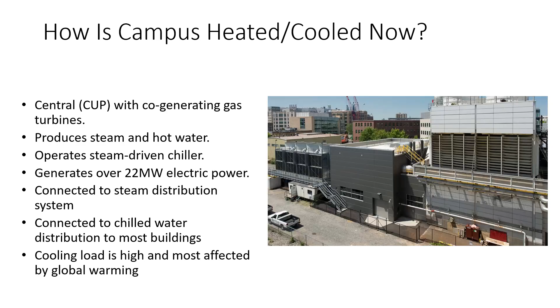Decarbonization issues with the existing plant: grid decarbonization is rapidly reducing the carbon benefit once touted for combined heat and power. Fossil fuel backup is necessary. Efficiency of 50 to 55% source to output. Low turndown rate of about 30%. High thermal losses in the steam distribution system of 10 to 20%. Non-zero losses in the chilled water system of 5 to 15%. And the hot water district system also has losses.